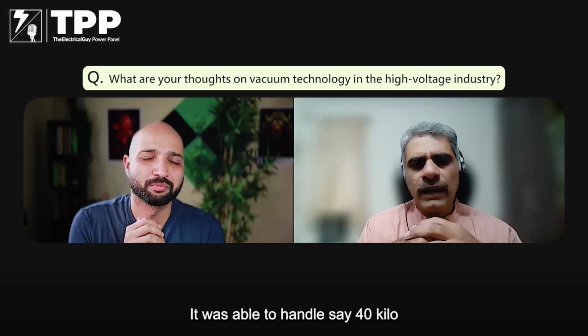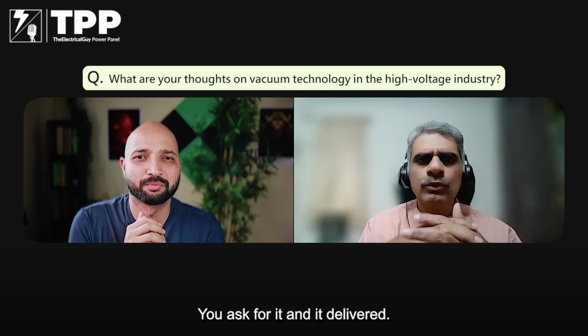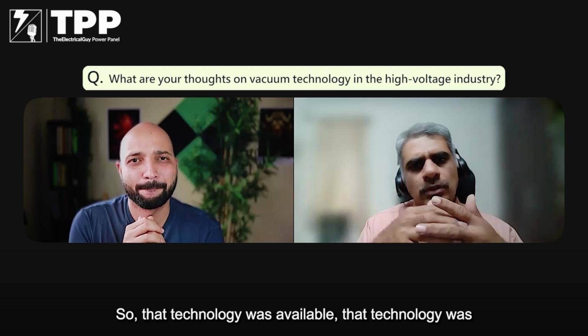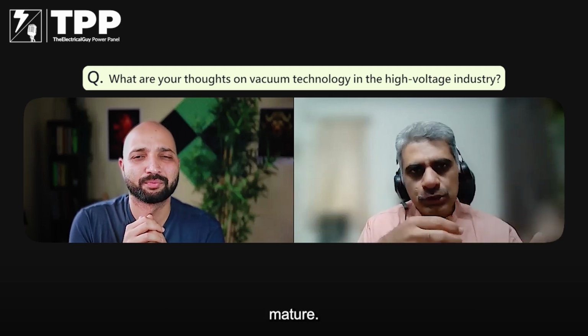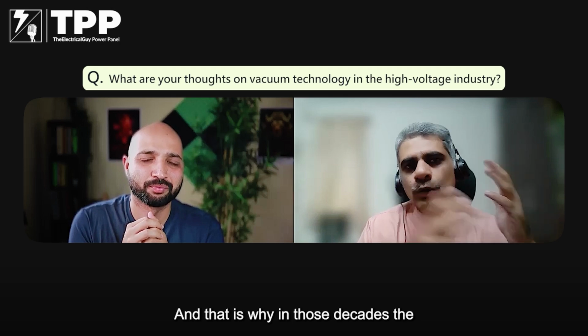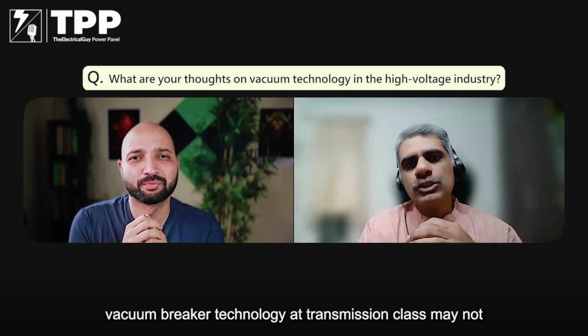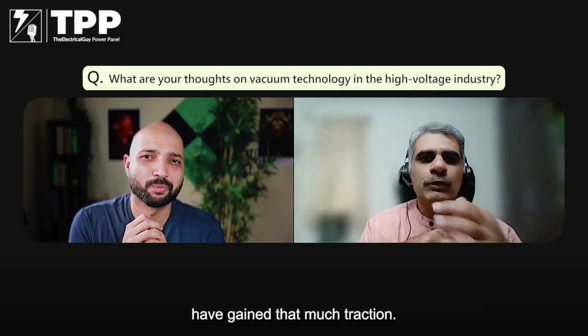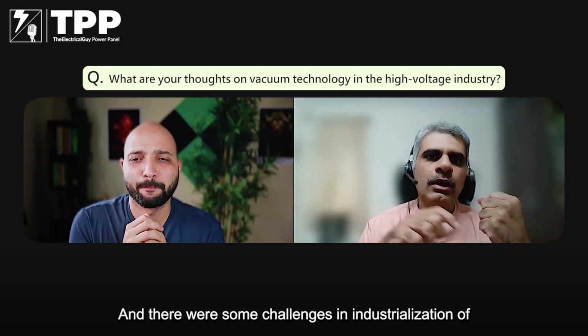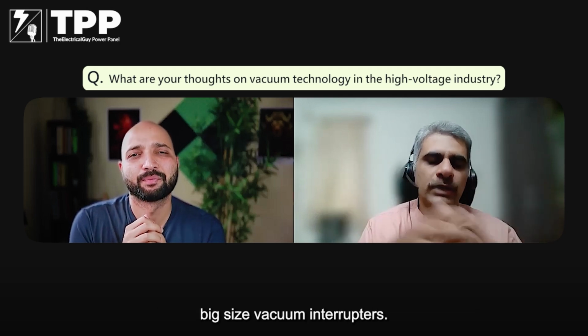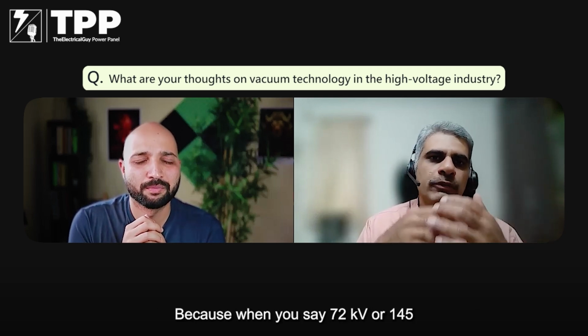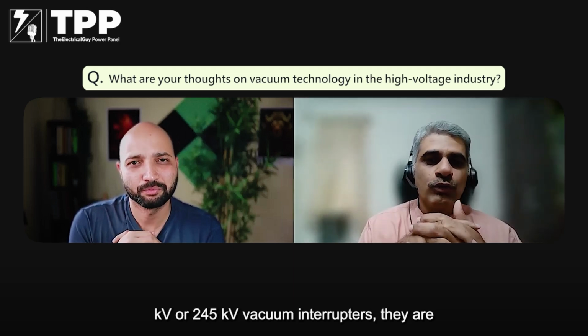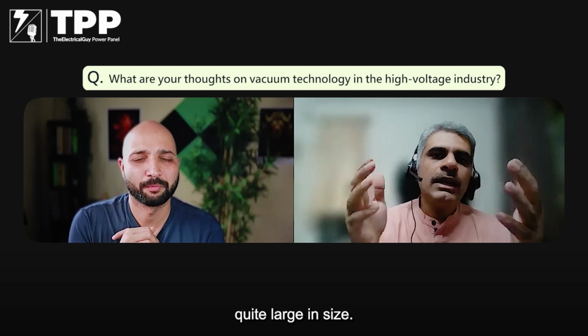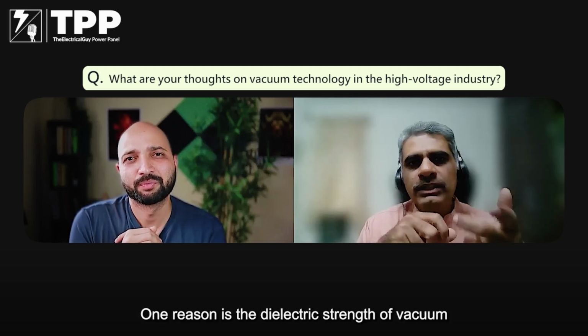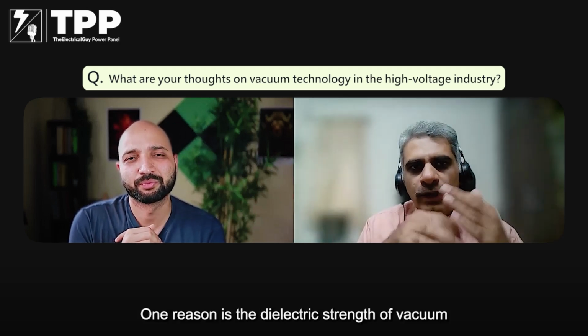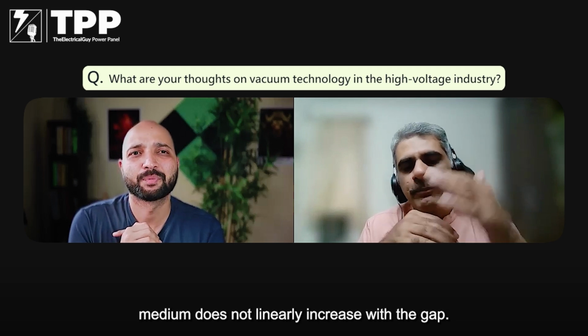It was able to handle say 40 kiloampere, 50 kiloampere. You asked for it and it delivered. So that technology was available, that technology was mature, and that's why in those decades vacuum breaker technology at transmission class may not have gained that much traction. And there were some challenges in industrialization of big size vacuum interrupters, because when you say 72 kV or 145 kV or 245 kV vacuum interrupters, they are quite large in size. And one reason is the dielectric strength of the vacuum medium does not linearly increase with the gap.